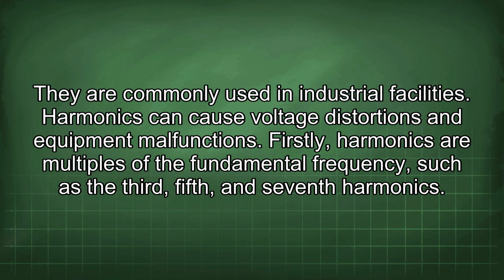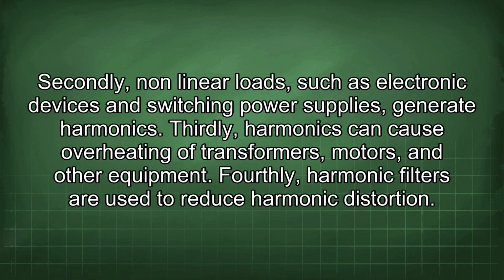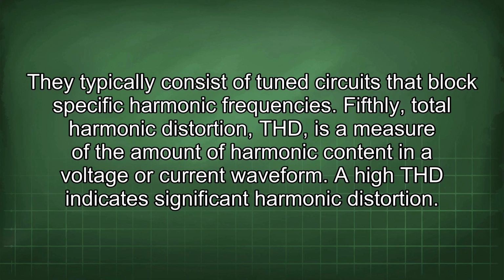Harmonics can cause voltage distortions and equipment malfunctions. Firstly, harmonics are multiples of the fundamental frequency, such as the third, fifth, and seventh harmonics. Secondly, nonlinear loads, such as electronic devices and switching power supplies, generate harmonics. Thirdly, harmonics can cause overheating of transformers, motors, and other equipment. Fourthly, harmonic filters are used to reduce harmonic distortion. They typically consist of tuned circuits that block specific harmonic frequencies.